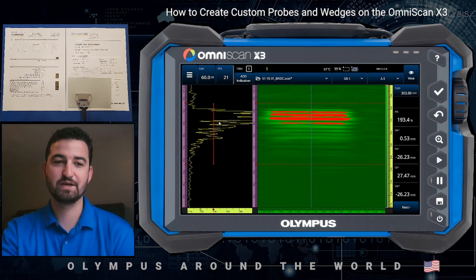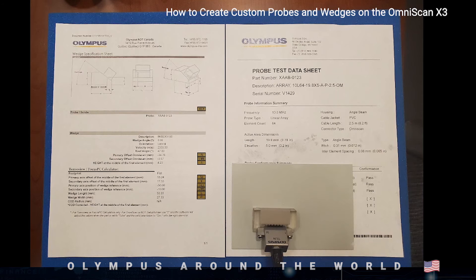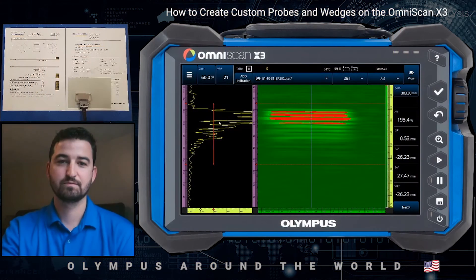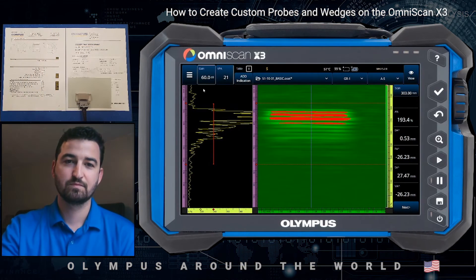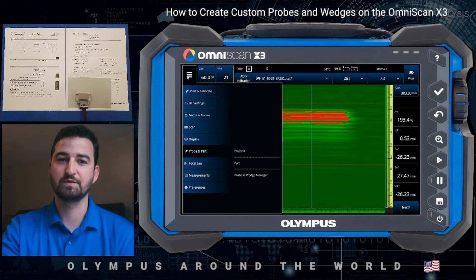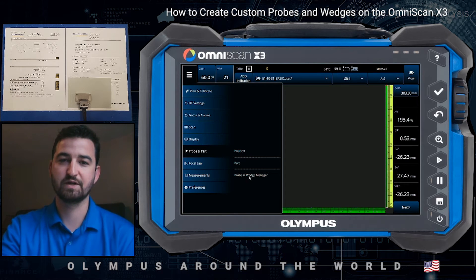Before we begin, you need to have your data sheets for the wedge on the left and the probe on the right. Then we enter the burger menu on the OmniScan X3. We go to probe and part, then probe and wedge manager.